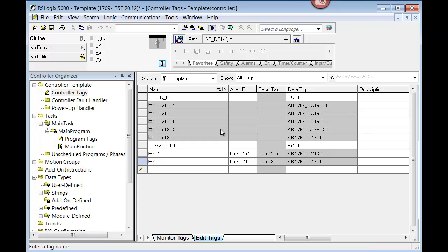And in order for the I/O module to function with the controller and communicate with the controller, you have to have a data structure in the controller that is a mirror image of what's in the I/O module. Otherwise, the I/O module can't send data to the controller memory unless the data it's sending fits exactly the size and structure of what's in the controller's memory. That's why I/O modules are all pre-declared as far as module defined tags.